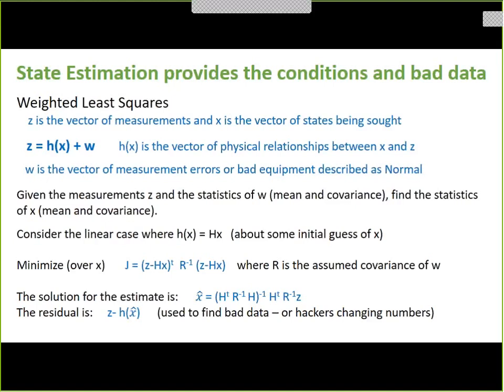It is what the measurements are telling me. I believe them. Everything is either good or bad. There's either alarms or there are not. The state estimation is more for the contingency analysis that's going to be used right after this. But there are some people that say to us, I don't believe the SCADA because it could be bad, and I want a state estimator.